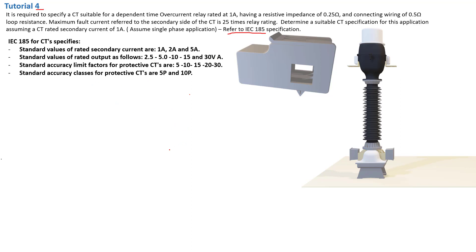We also have accuracy limit factors for protective CTs, which are between 5 and 30. The accuracy limit factor is the number that determines the magnitude of the current that can flow through the primary of the CT. For example, if we have 1,000 amps flowing on the primary and we take an accuracy limit factor of 10, that means 1,000 times 10 — that's how much current can flow through the primary before the CT reaches saturation.